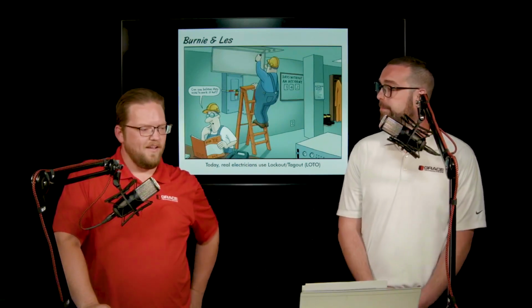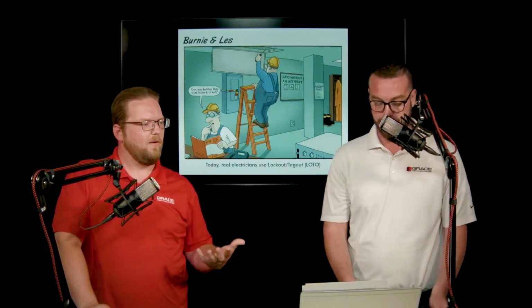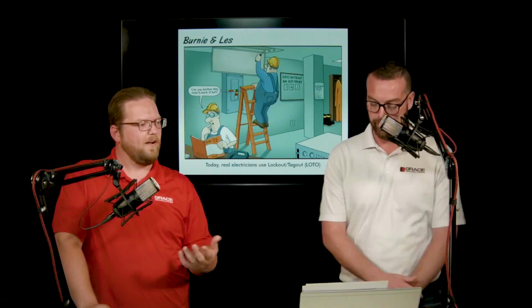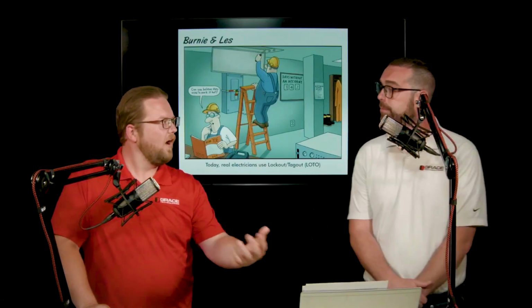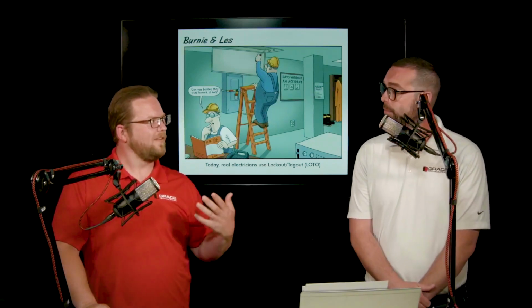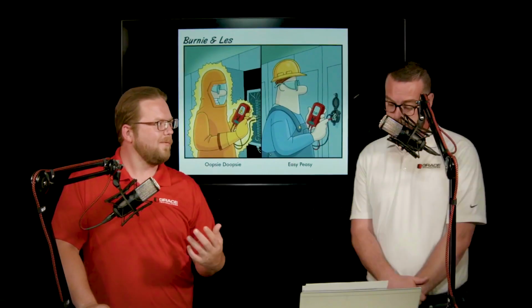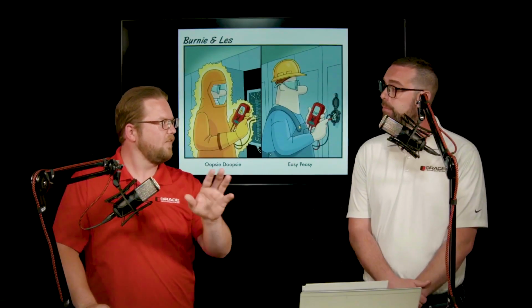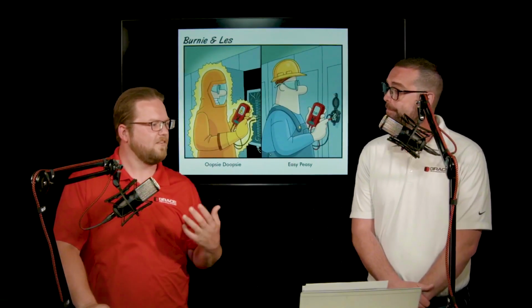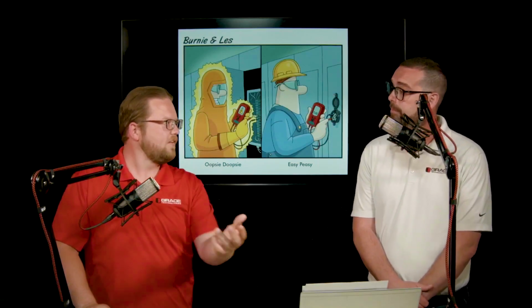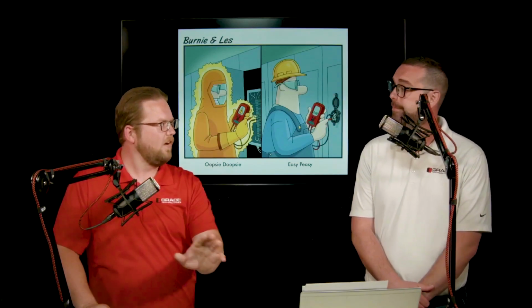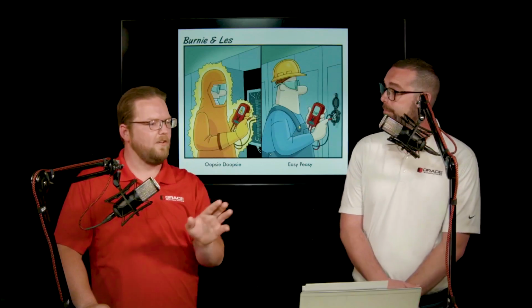Yeah, and that brought in a few questions. The way we install that, we're bringing the wires to the source power, bringing that to the panel front so that you can test there. And then a lot of questions came in on how are we confident that that is touch safe? Is there not still a shock risk? If you're going to 1,000 volts and you're testing there with no fuses in between, how can we make sure that you can go up and touch that?